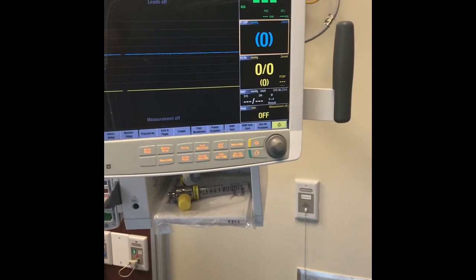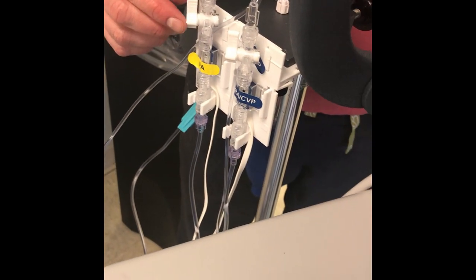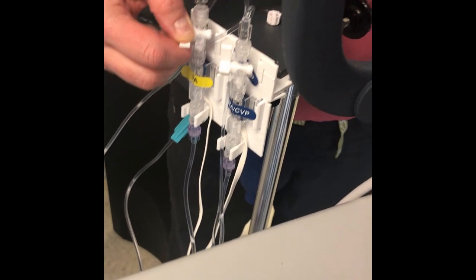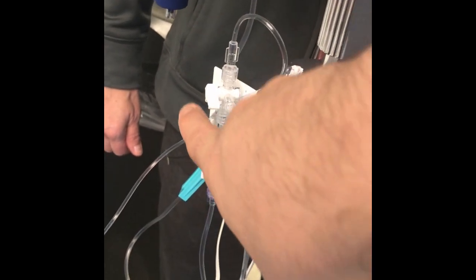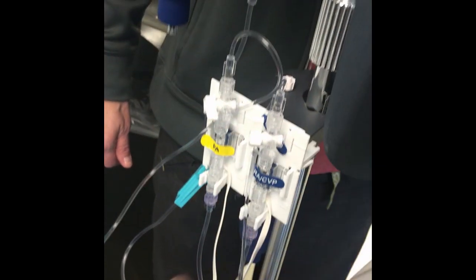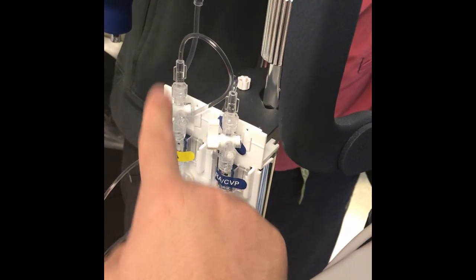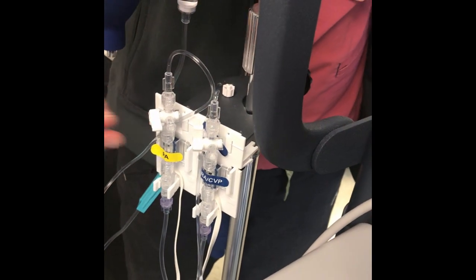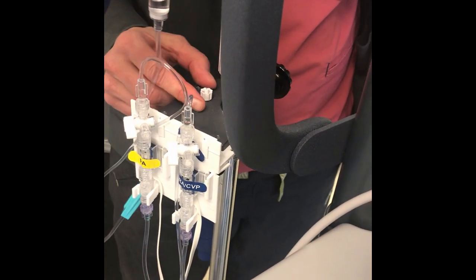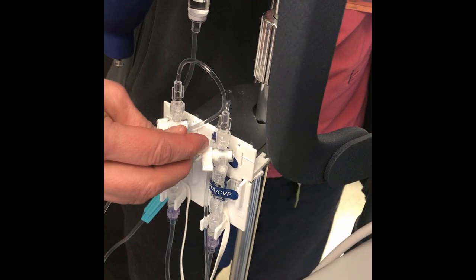After you confirm the zero position, you go back to your sensors and you make it look towards this way, so this outlet is closed and the pressure will be reading through the vertical. Same thing for the CVP. It would be nice also to close them after you're done.